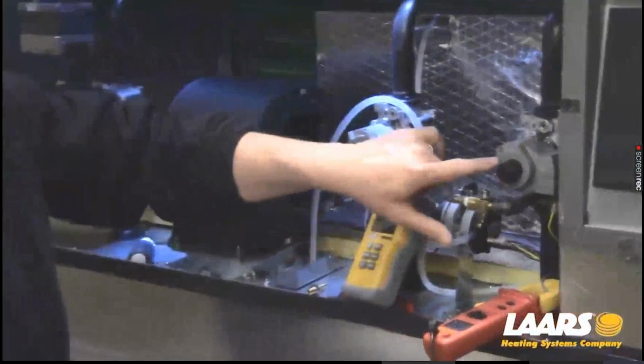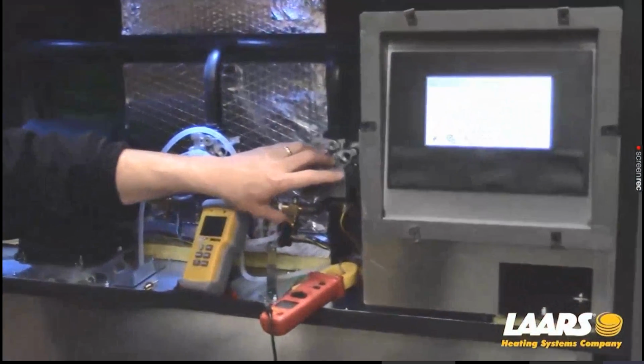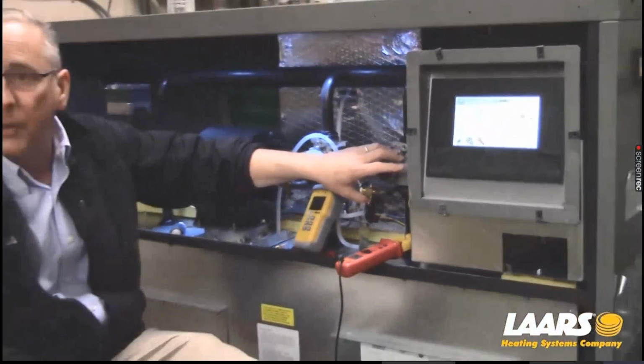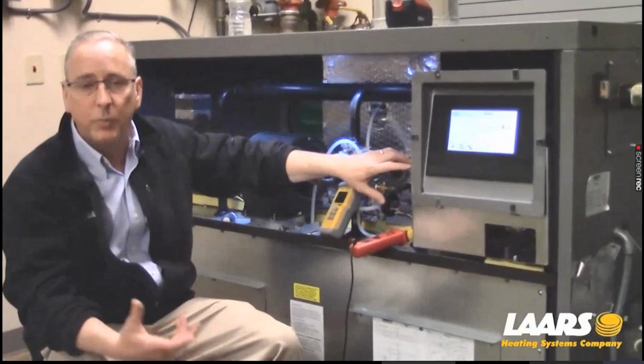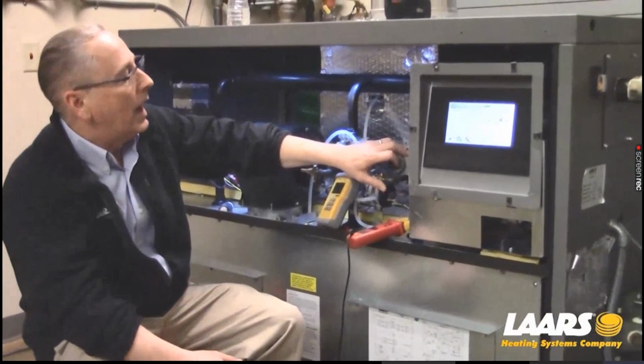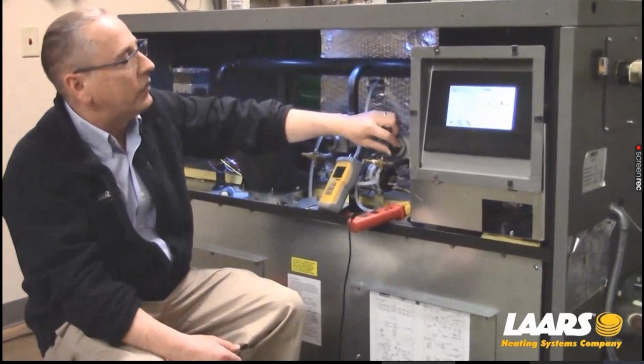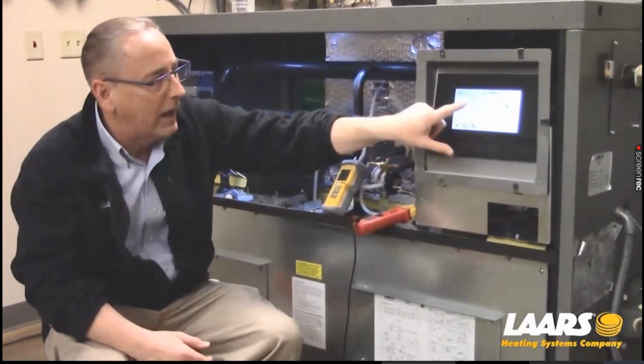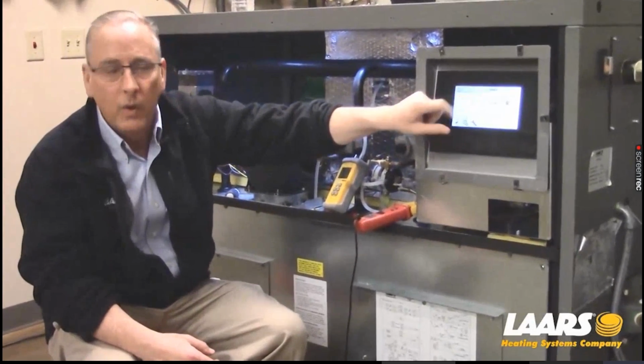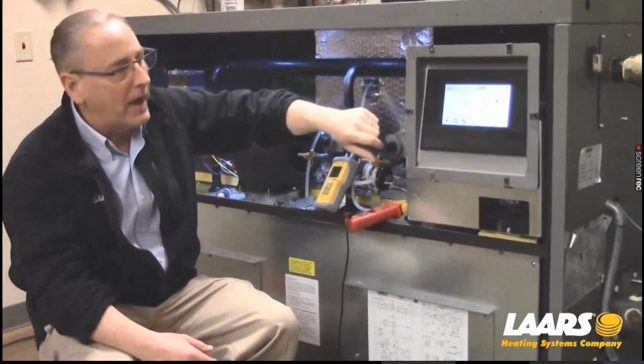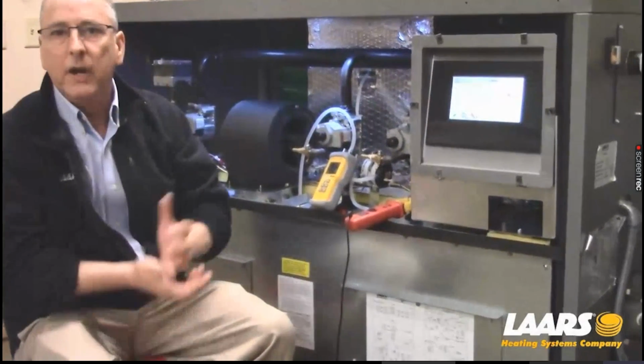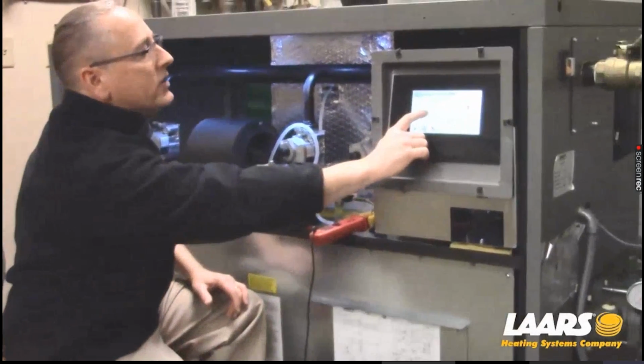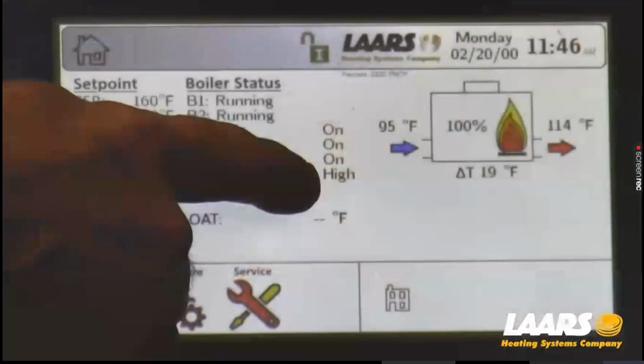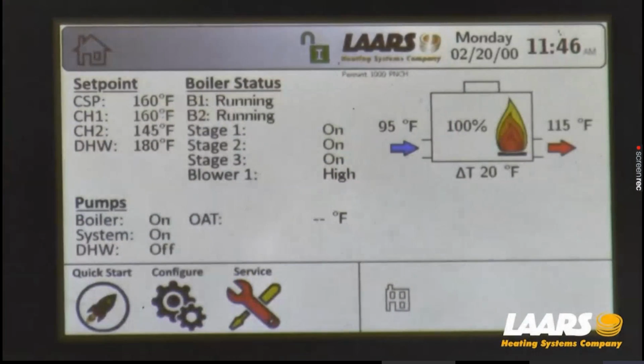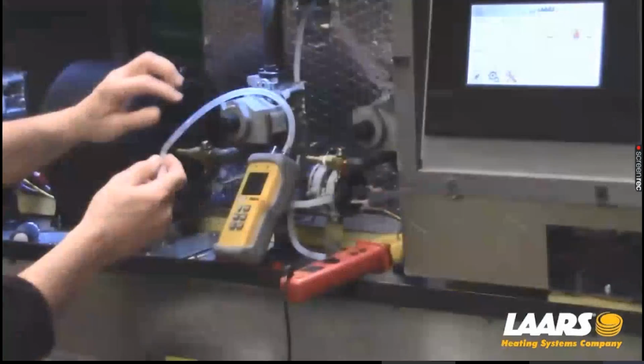I originally shut these valves off. You can leave them on, but keep in mind you may preheat your loop depending on the time of year and what your building demand is. Also, if you shut these off in stage 2 with lockout, it'll read lockout. In that case, turn your valve back on, get the reset on the screen, wait, and you'll then see. So in this case right now, stage 3 is in the on position, and I can check my last valve.